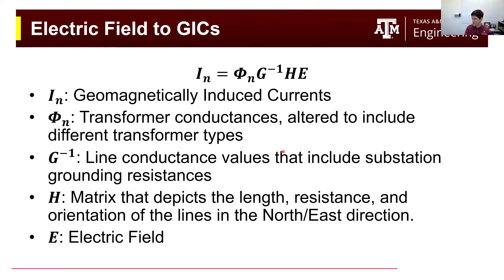So what we've done, let's see if I can go forward, is we approximated about 5 zones using our synthetic grid. We can also use the real grid as well. But we used about 5 different zones, and within each of those zones we assume the electric field is uniform. So the question we're asking is: how many GIC measurements do you need in order to estimate the E field using neutral current monitors, GIC neutral current monitors?